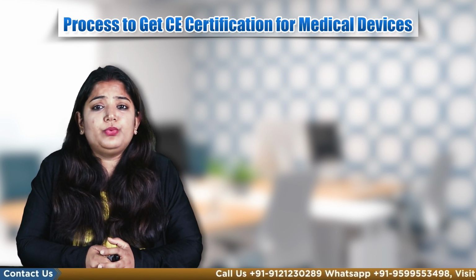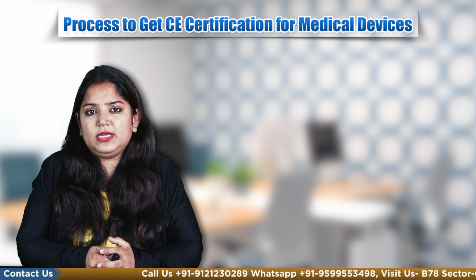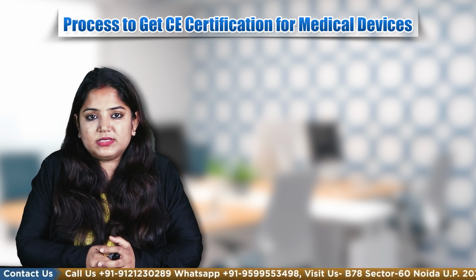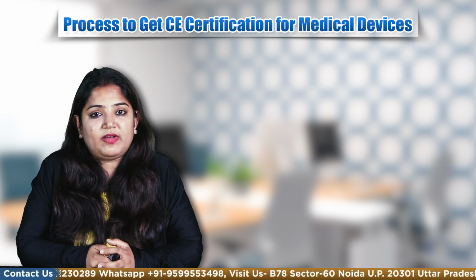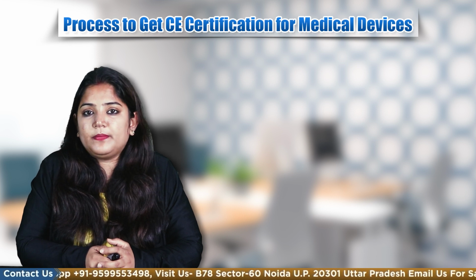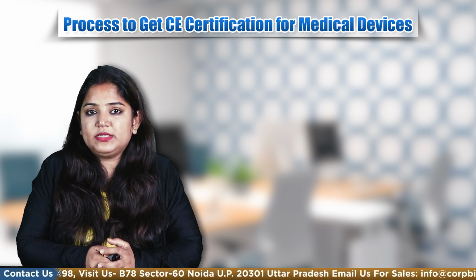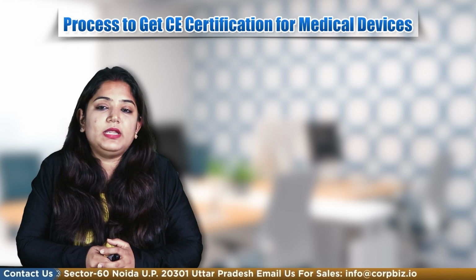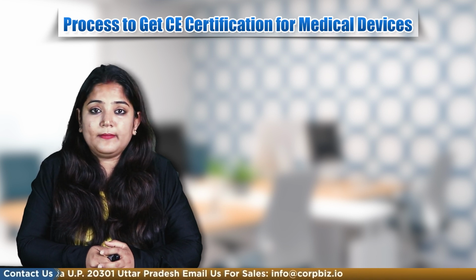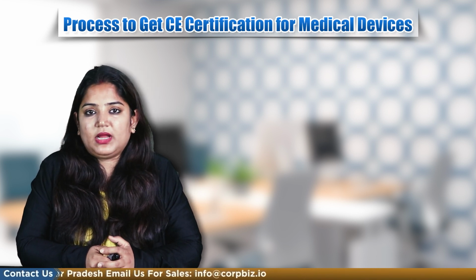In this video, we will discuss the process to get CE certification for medical devices. Most medical device makers must have their quality management system authenticated by an independent notified body, NB, by securing CE marking.